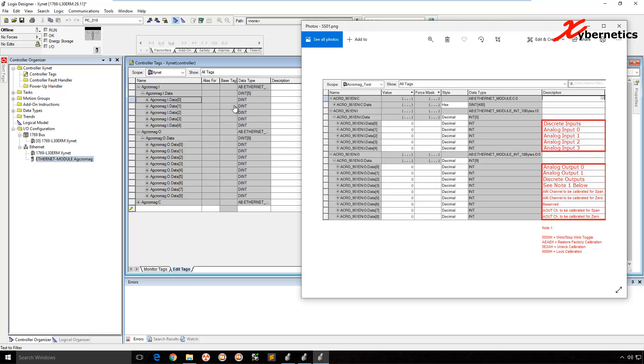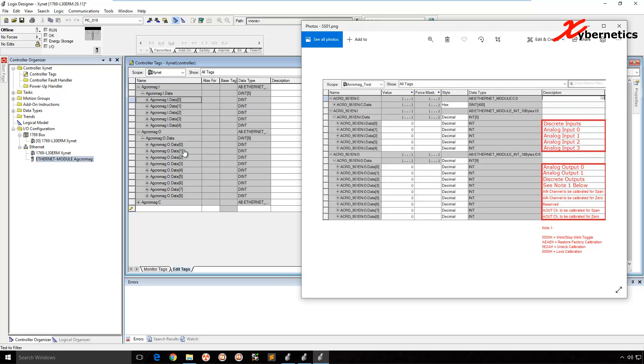That's how you get for this device. And element one to four is your analog input. These are unipolar counts. So it goes from zero to 20,000, exactly like Allen Bradley's AI module. So it goes from zero to 20,000. And as for the output here, array element zero and one, the analog output zero and one. Again, analog output, they are unipolar as well. It goes from zero to 20,000. So if you have like a valve opening from zero to a hundred percent, you're going to have to scale it to zero to 20,000. That's what I mean by that is a raw signal that you are reading or writing to.